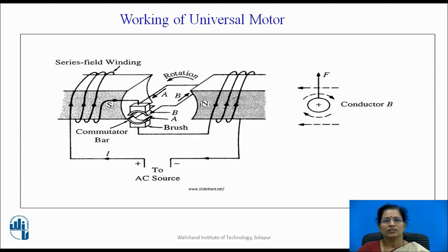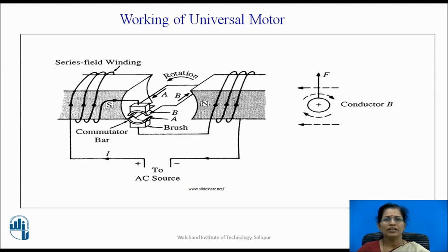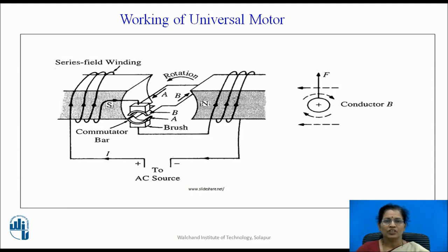If we connect AC supply to that motor, the direction of the current through the series field winding and the armature winding both are reversed for the positive cycle and negative cycle. So the torque created on the current carrying conductor has the same direction. Therefore, a unidirectional torque is created due to both the positive cycle and negative cycle. Thus, unidirectional torque is created due to AC supply.